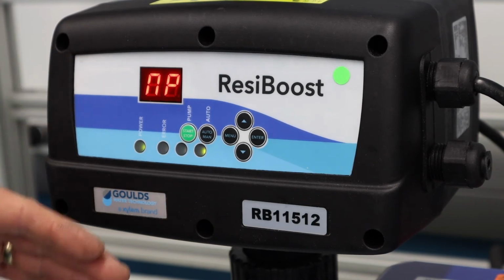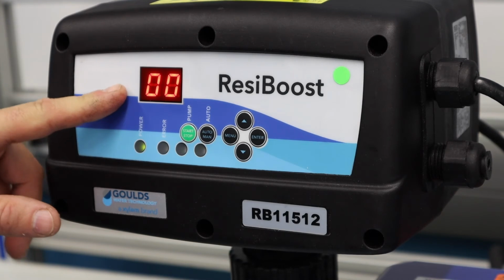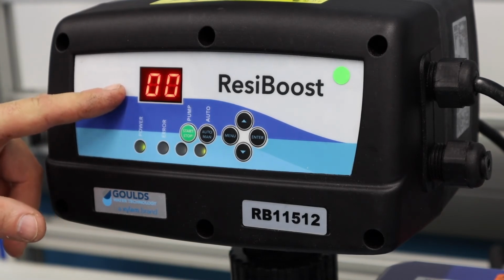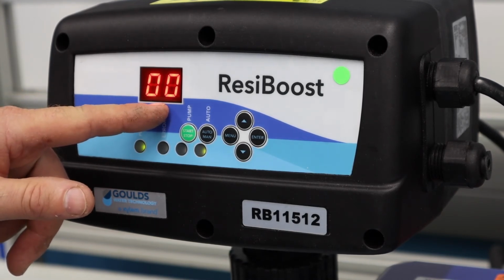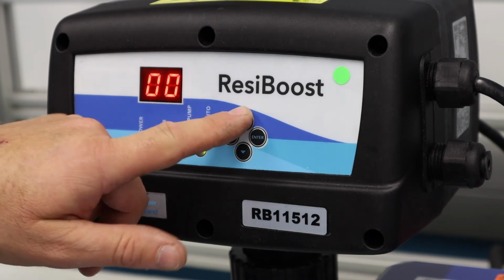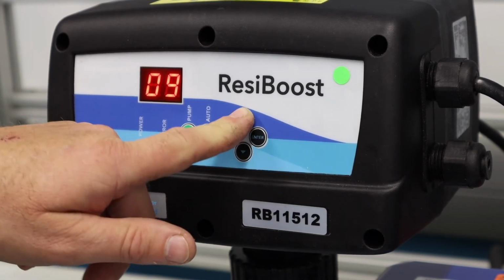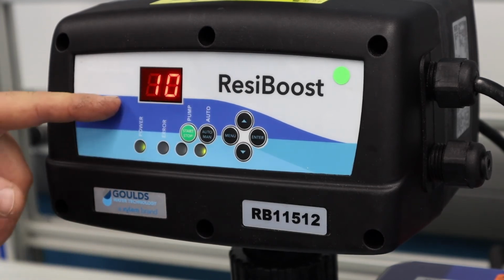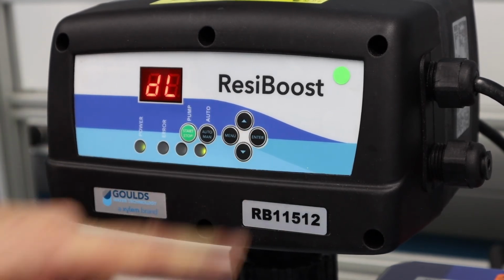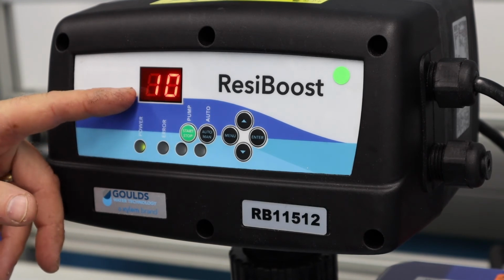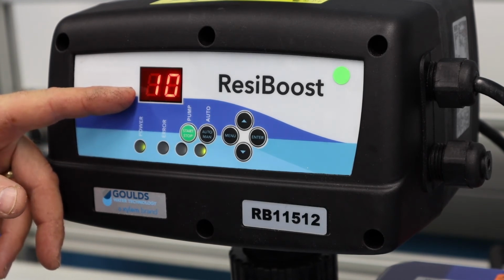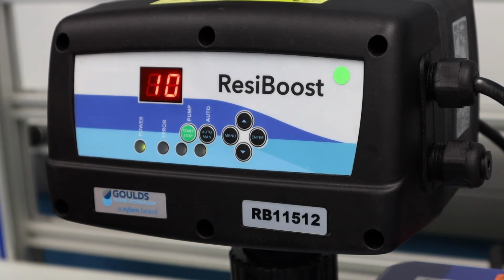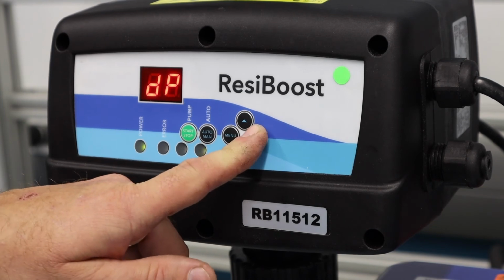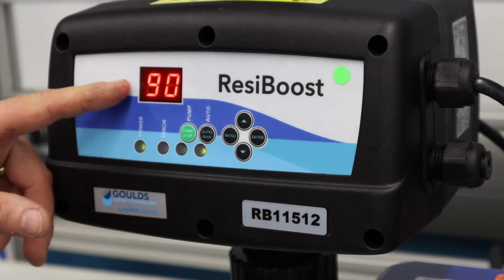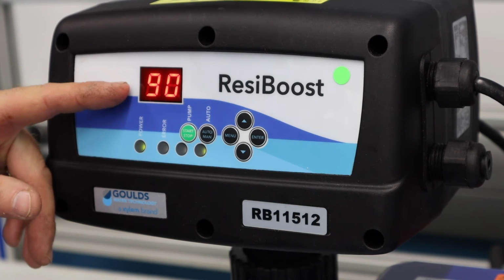But for our case, there's another part to this which I want to show you, which is the delay time. And if you put in 0, you're not going to see the DL parameter. So just for demonstration, let's say I want 10 psi min pressure protection. And so we can see here the next is the timer. So this is 10 seconds. So that would be the next parameter. So I'm going to hit the enter button.